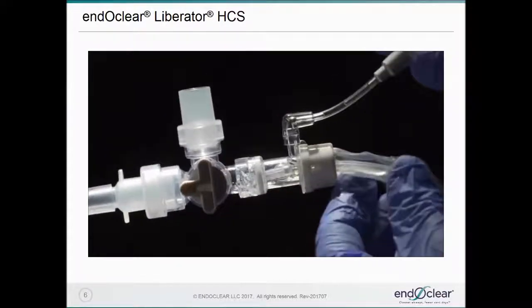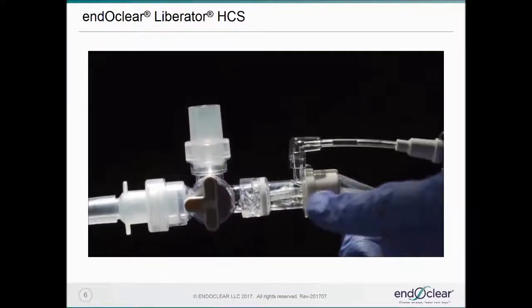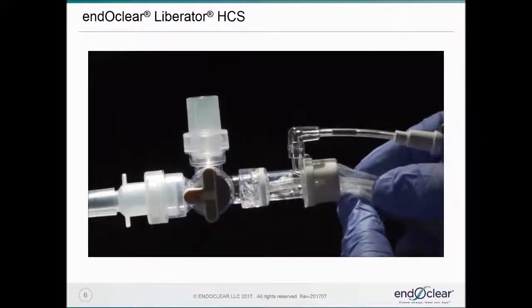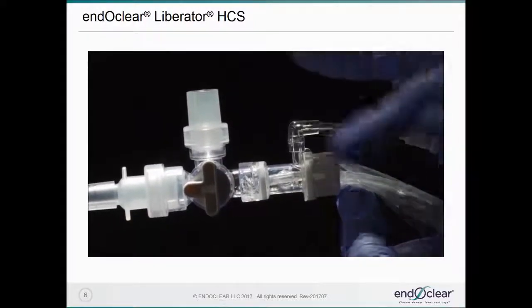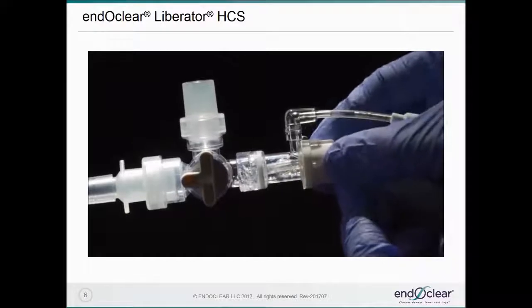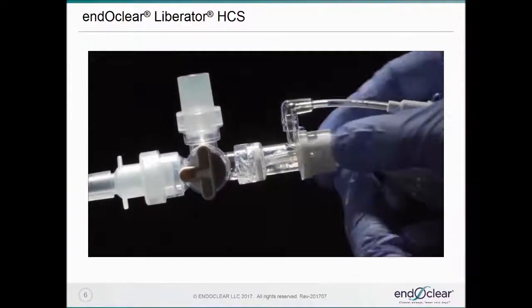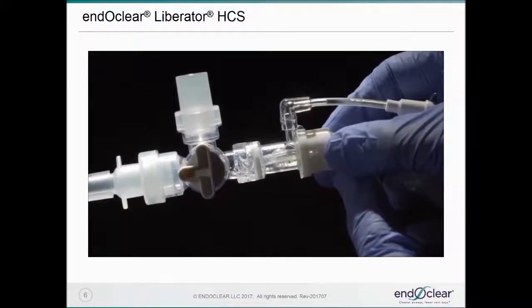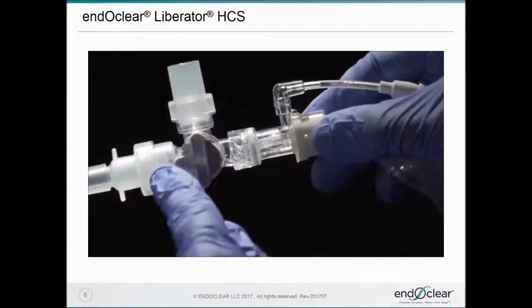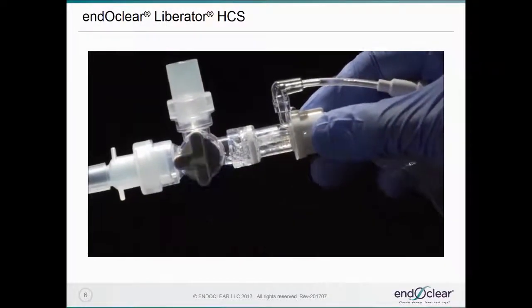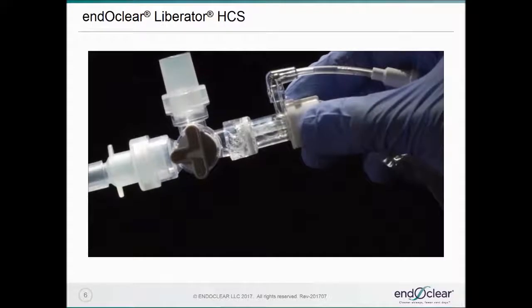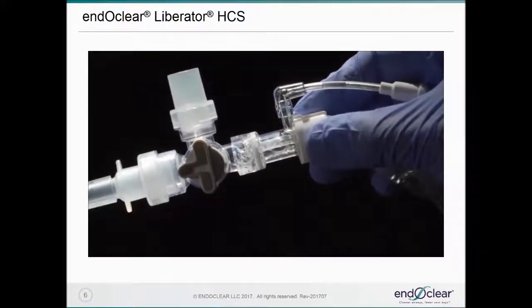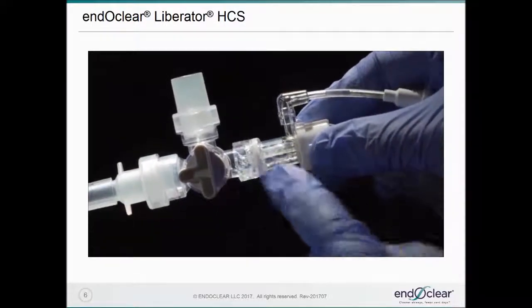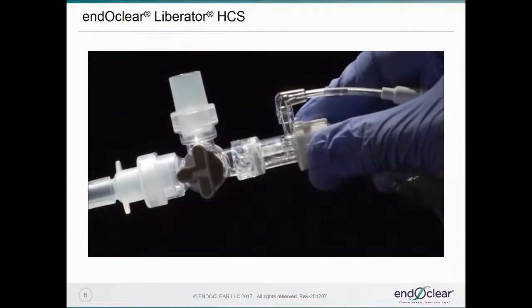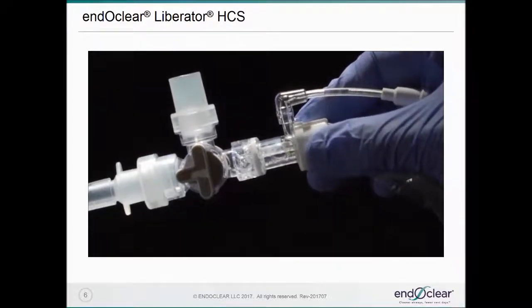The saline bulb is removed, and as you can see, the residual pulmonary secretions have been taken into the suction catheter and the wall waste by using suction applied at 150 millimeters of mercury. We now have a fully open endotracheal tube at the lowest work of breathing possible for that size tube, and we have a clean suction catheter in its cleaning chamber ready for its next required use.